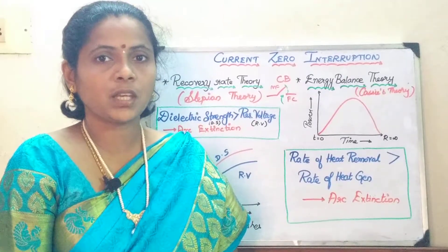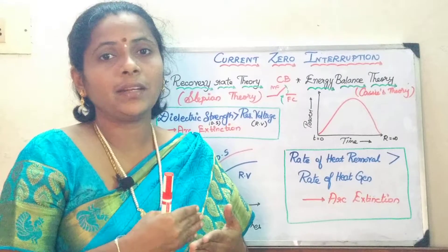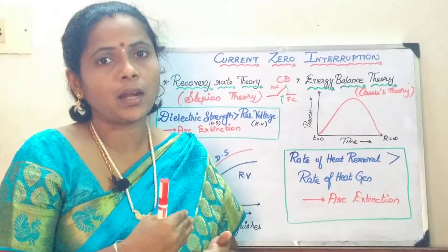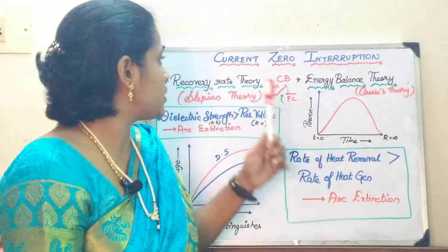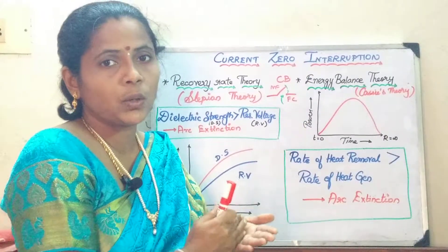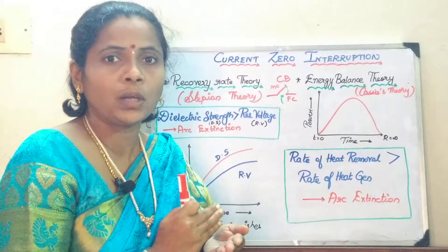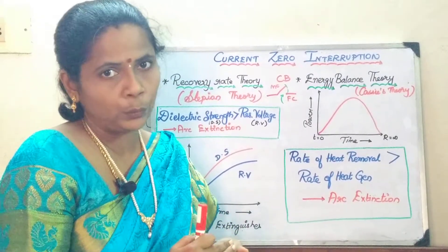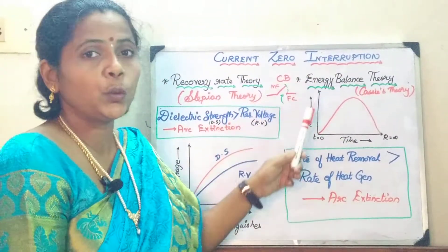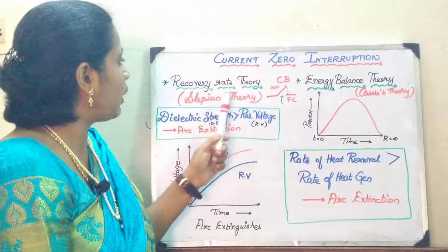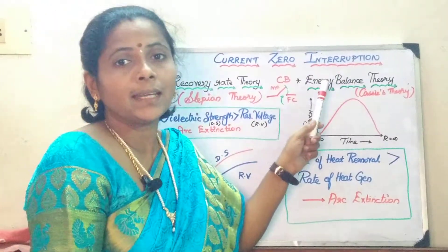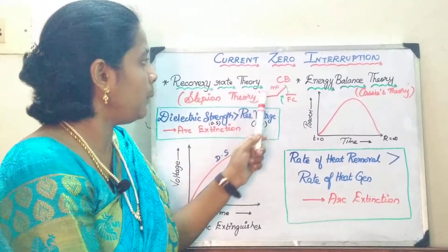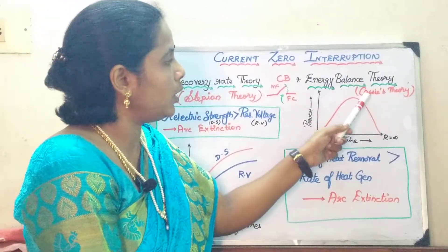In the earlier session, we have seen about the two current interruption methods for circuit breakers. One is the high resistance method, another is the low resistance or current zero interruption. This current zero interruption is usually applied only for AC circuit breakers, where you are trying to quench the arc at natural zero. In this current zero interruption method, you have two types: one is the recovery rate theory, another is called the energy balance theory. The recovery rate theory is also called Slepian theory, and the energy balance theory is called Cassie's theory.